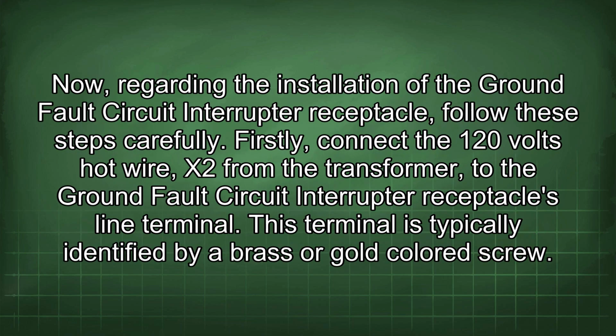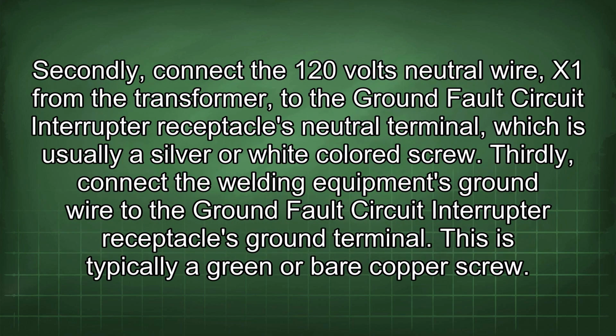Now, regarding the installation of the ground fault circuit interrupter receptacle, follow these steps carefully. Firstly, connect the 120 volts hot wire X2 from the transformer to the ground fault circuit interrupter receptacle's line terminal. This terminal is typically identified by a brass or gold colored screw. Secondly, connect the 120 volts neutral wire, X1, from the transformer to the ground fault circuit interrupter receptacle's neutral terminal, which is usually a silver or white colored screw.